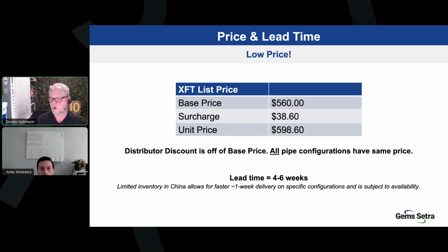This will bring me back to those programming parameters, right? If in fact you're in a pinch and you absolutely need something, you can configure the product regardless of how it's ordered. You can configure it to suit your application, right? You can change the pipe material via programming. You can change the media type. You can change so many different parameters, and you can actually dial it in to match your application regardless of what was ordered, right? However, that comes with a risk because if you ever reset or if something happens and the product resets, it's going to reset to its default values. Also, the part number and serial number that are recorded into the device never change. That's always going to be what you originally ordered. So just keep that in mind.